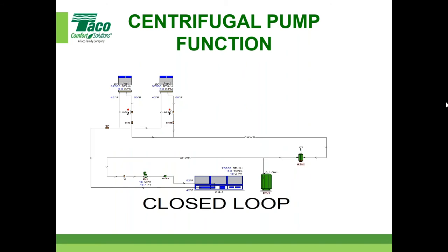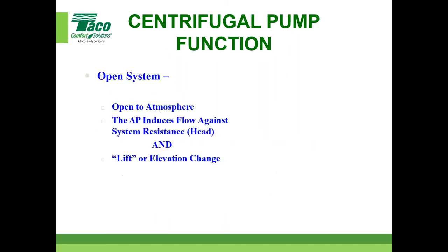And here's a simple picture of a closed loop system. I mean, it can't be any simpler than this. A little air-cooled chiller pushing the water through here, goes through a couple of coils and back through an air and dirt separator, through an expansion tank, and back in. There's no place in here where it's open to the atmosphere. So that's a simple closed-loop system. And don't go copying this and using it as a design. It's a starting point, but I wouldn't necessarily use it as a design.